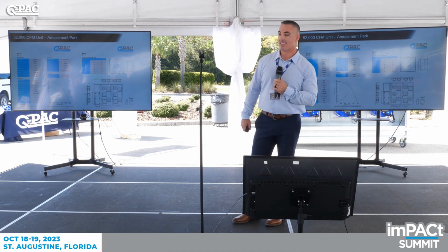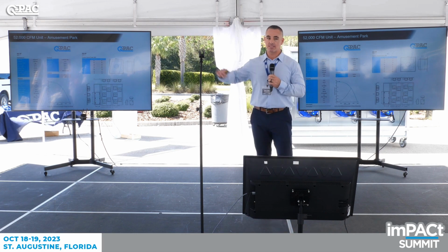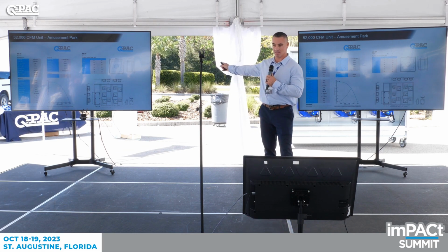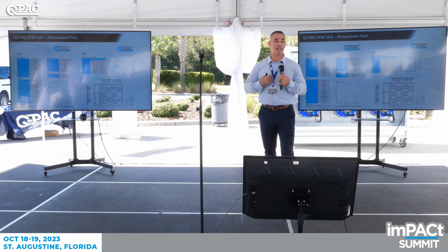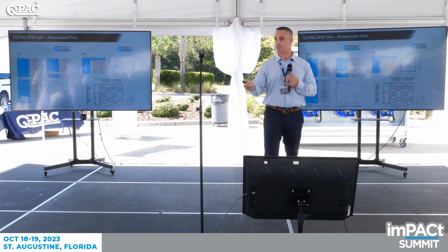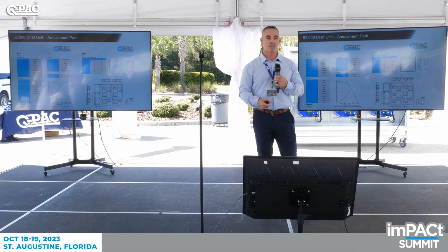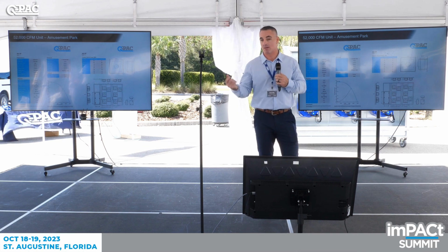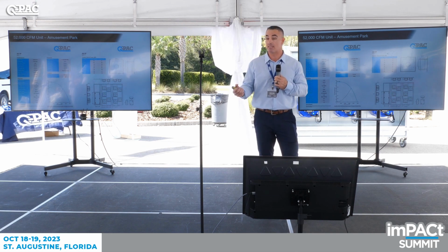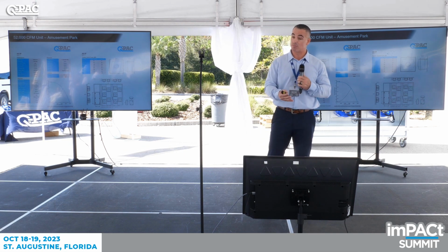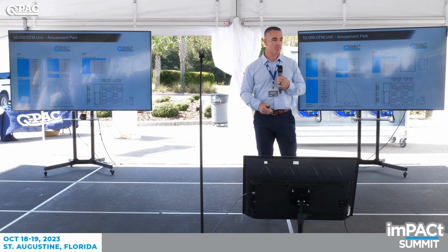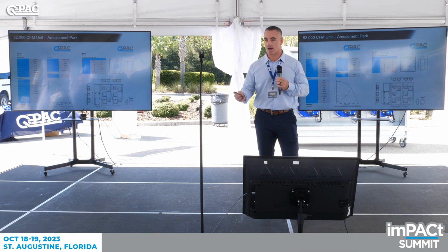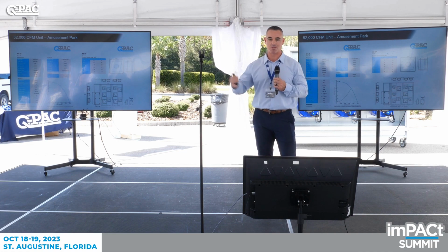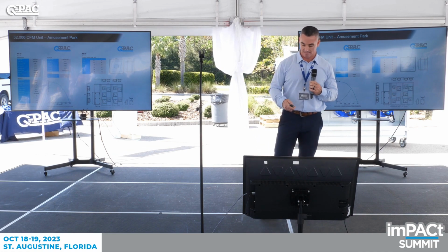Yes, exactly. It's not a TAB of the system, it's a TAB at the air handler level. I have my own pressure ports, tubing, and gauge. So when I go to job sites, a lot of times I'll bring my gauge. If I don't know the CFM, I'll at least know what pressure we're running at on this particular one. Most of us in here can probably do fan laws and figure out, if we're off, where we're at, and where you're going to be.